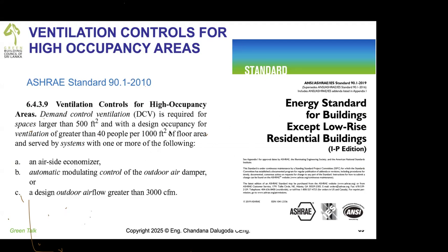So ASHRAE standard 90.1 give demand control ventilation. Another one, demand control ventilation. When occupancy exceeding 40 people per 1,000 square feet or 4 people per 100 square feet, we'll have to use demand control. With a CO2 sensor, it works only for demand. Otherwise, no airflow supplied, less airflow supplied.